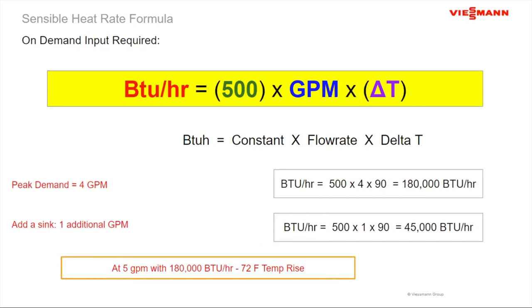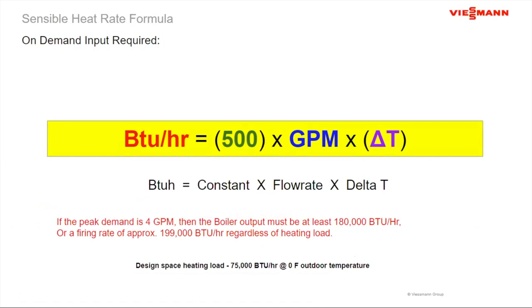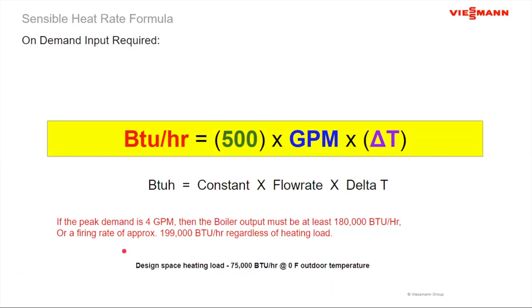So I take that 180,000, that's the output. So it's telling me that for 4 gallons per minute as the target, generally I'm looking at a boiler input of about 199,000 BTUs, okay? So that becomes my domestic hot water load. Now, quick refresher. My space heating load is 75,000 BTUs per hour. So all of a sudden, when I start to do a combi with domestic hot water, I've increased the size of the boiler over 2.5 times, almost 2.5 times, to be able to meet the hot water needs. And this is a lot of times the issue when I start to look at combi boilers with a fairly hefty domestic hot water demand. The domestic hot water demand far exceeds the space heating demand, and that becomes the driver when you start to size with combi boilers, okay?